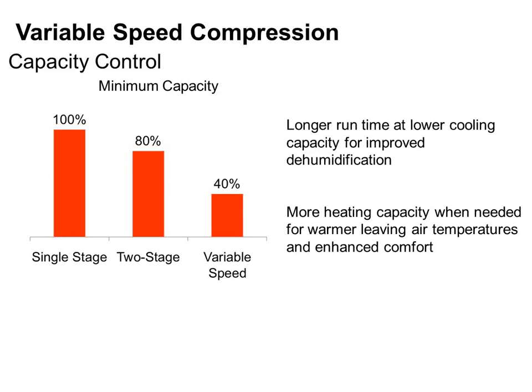In your mind, you're thinking, oh, when only one stage is running, I've got 50% capacity. Well, that's not actually true. Almost every 2-stage heat pump, in fact, all the ones I could find as examples, the best one was at 68% capacity with just one stage. The highest one was 80% capacity. So you think it's 50%, but really it's more like 70, 75, something like that.